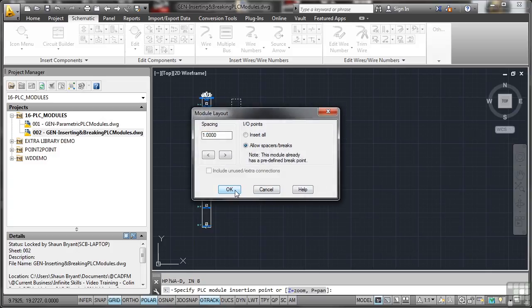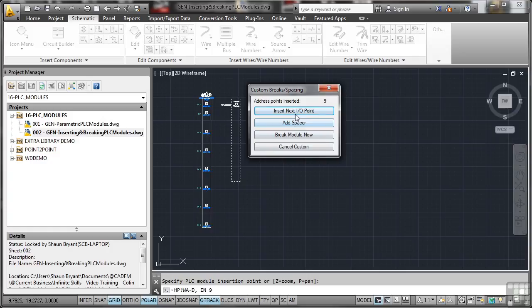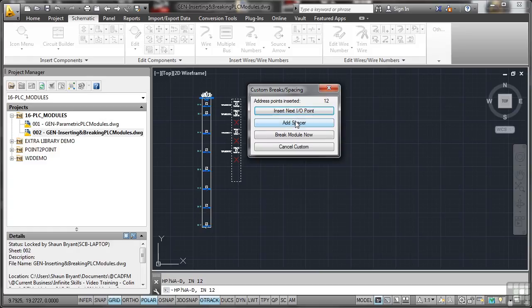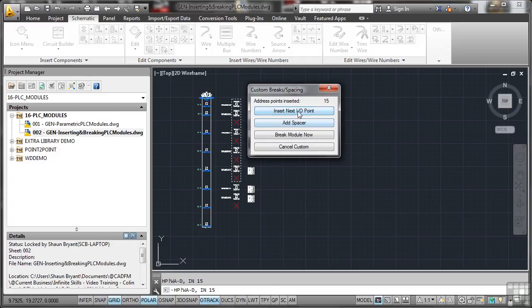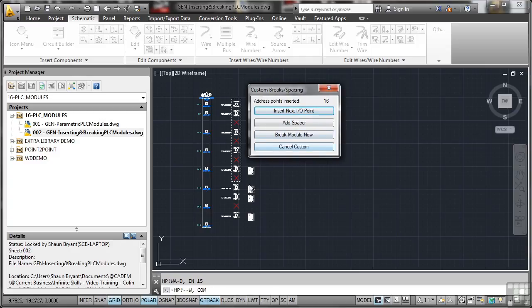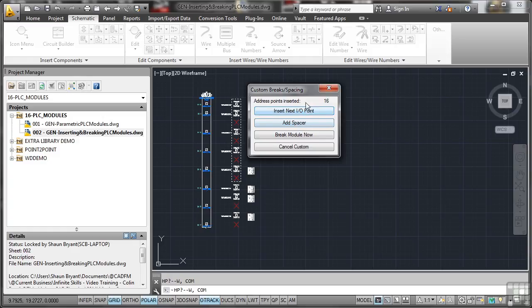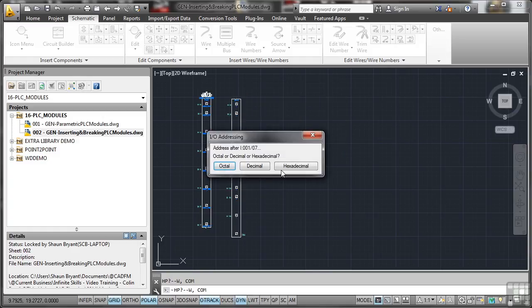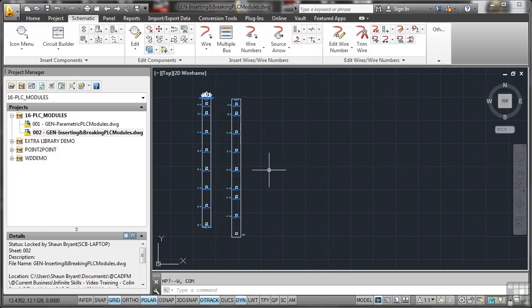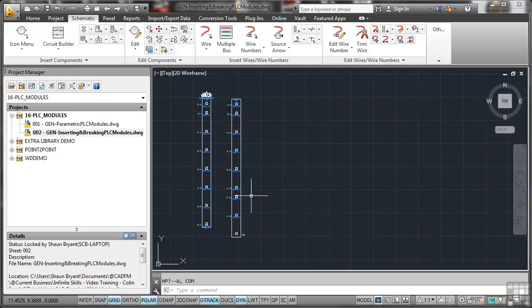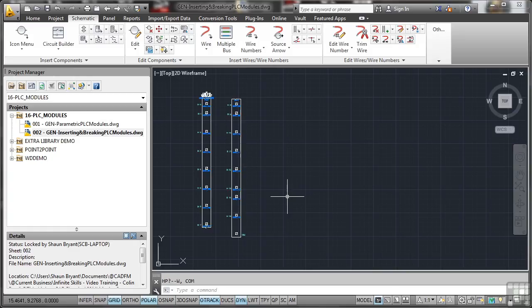Spacing there. OK that again. Insert next IO point. Add spacer. Insert next IO point. Add spacer. And I keep going until obviously I hit my 16 input output points. Now because I've broken this in a weird way, this is quite amusing now. If I keep going and add some more spaces there, it just keeps going. So if I go add spacer now, can't go any further. I'll just do decimal for now. Did you notice that it was going off the end of the PLC module? And what was amusing was it looked like it was actually going to go off the end and just into space there. The good thing about AutoCAD Electrical, because this is parametric, it'll actually set it up for you. So it actually sets up the length. You're literally creating a custom PLC module using that insert and break tool. So try and use parametric PLC modules wherever you can, because you can customize them to fit into your AutoCAD electrical drawing.